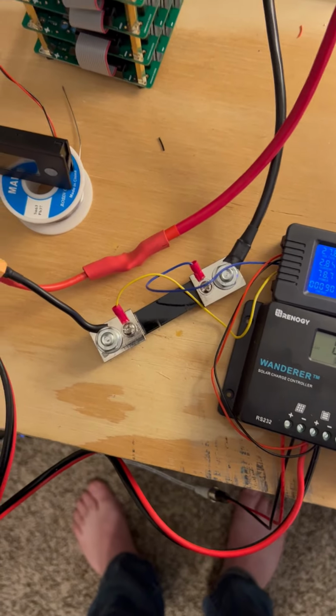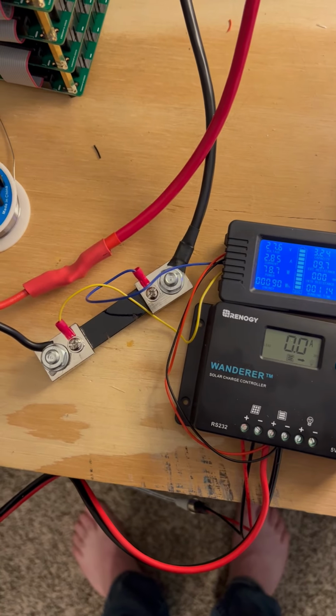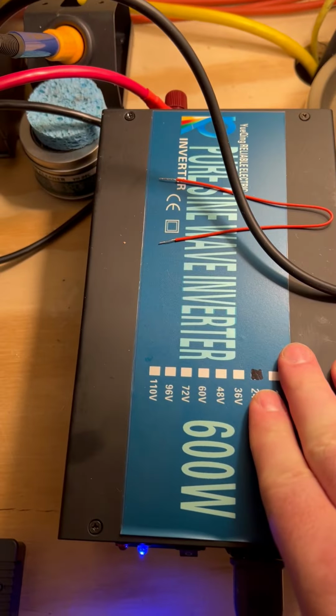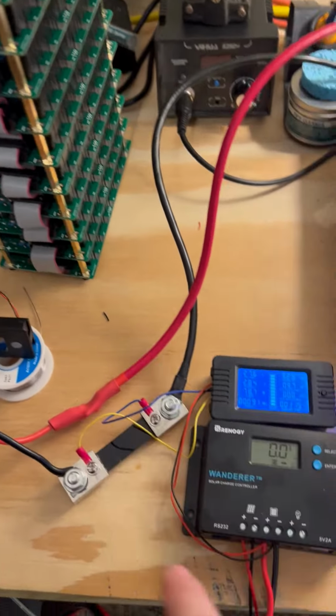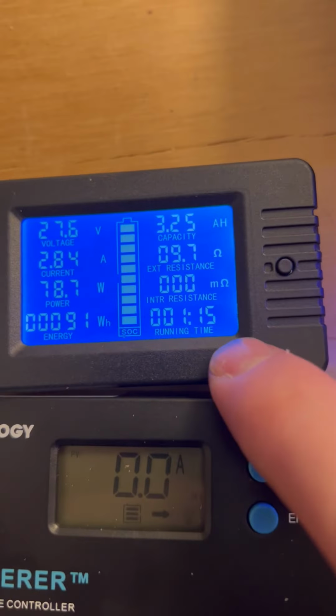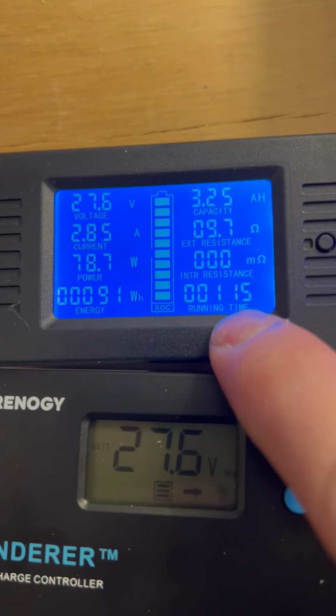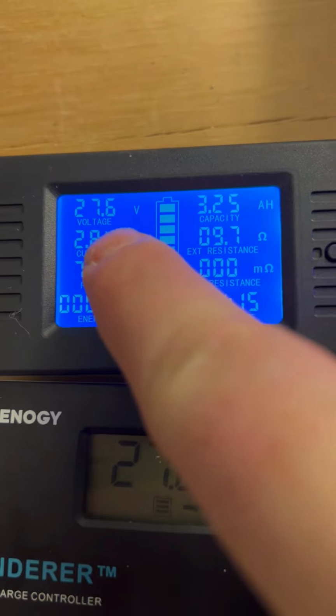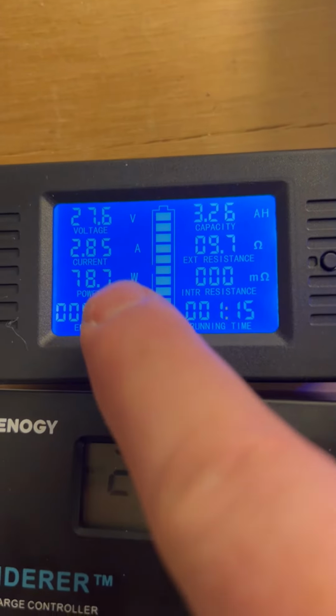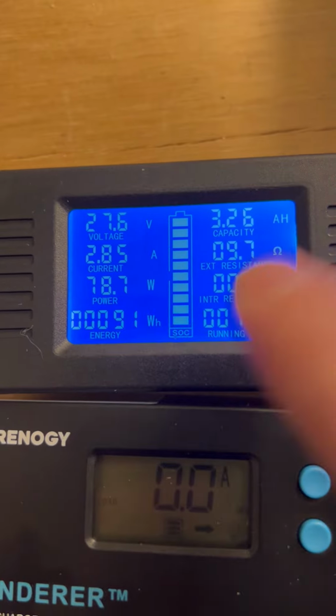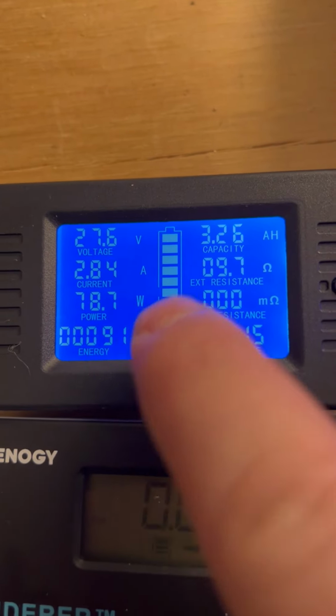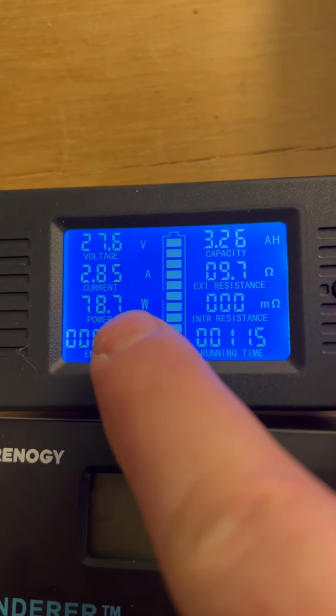So I'm trying to run it down to see how long it lasts. I've got my fan running at full throttle, plugged into a 600 watt inverter running directly off the load of this battery. So far it's been running for an hour and 15 minutes. It's down to 27.6 volts, and the inverter and fan are pulling 2.85 amps, 78 watts.